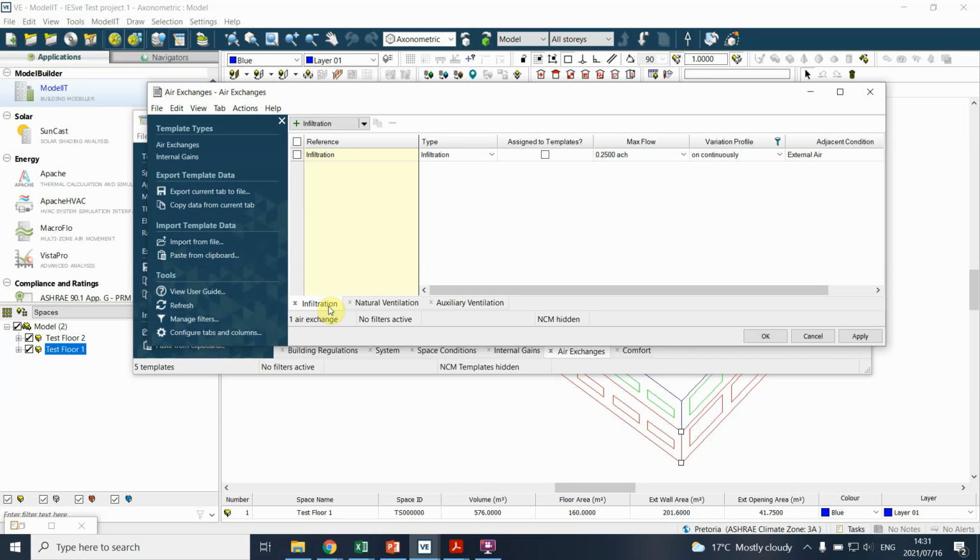There are still questions about how appropriate it is for temperate conditions, but either way, in terms of modeling it, I think you have to have some idea of what the infiltration rate is for your South African conditions. So you can range from a highly sealed, well-designed set of windows at about 0.25 liters per second per square meter to 7.13 or 7.3 liters per second per square meter for a leaky building, effectively. So it's quite a range that you could use.